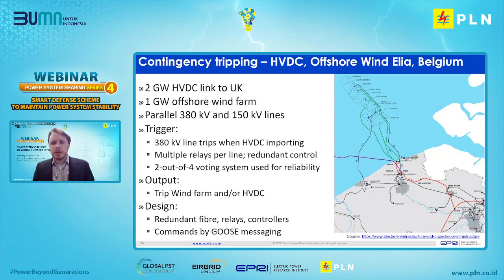This is a very similar scheme in Belgium, where a large offshore wind farm was connected, 1 gigawatt of offshore wind and a 2 gigawatt HVDC link. Now, in this case, there is a 380 kV line and a 150 kV line in parallel. And much like the previous example, there are contingency cases where if the 380 kV line trips, the 150 kV line might be overloaded. This is very similar, but the technology used is very different in that it's such a critical line with such a large amount of power.